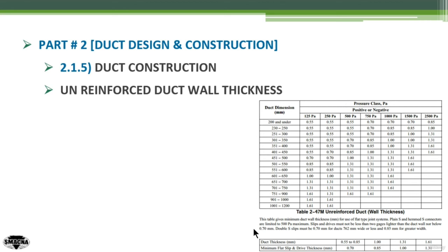This means the table gives the minimum duct sheet metal thickness, and that the joints and seams should be two gauges thicker than the duct wall. A smaller sub-table below compares the duct sheet metal thickness against the minimum flat slip and drive thickness, giving an equivalent thickness for the joint and seam of the duct.